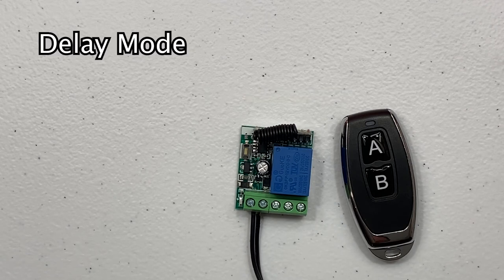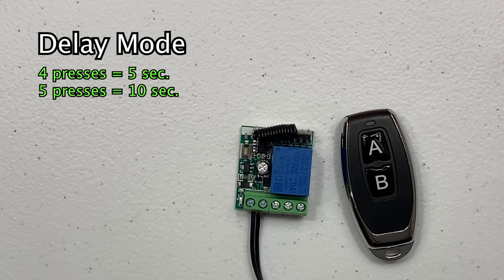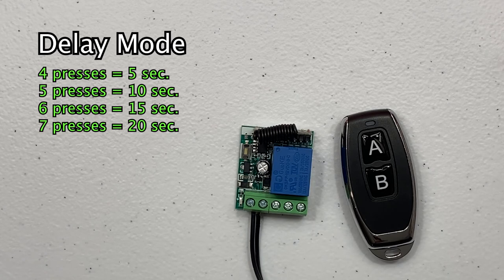To set the relay into delay mode, repeat the same procedure but press the button four times for five seconds, five times for ten seconds, six times for fifteen seconds, or seven times for twenty second timer.